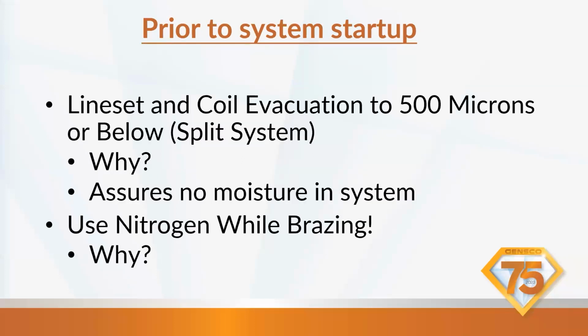Prior to system start, line set and coil evacuation, we want to be below 500 microns. Why do we want to make sure that we're below the 500 microns? Because it assures there's no moisture in the system. So when we assure that there's no moisture in the system, once we open up the valves to release the refrigerant, the only thing we want in those refrigerant lines are refrigerant and compressor lubrication oil.